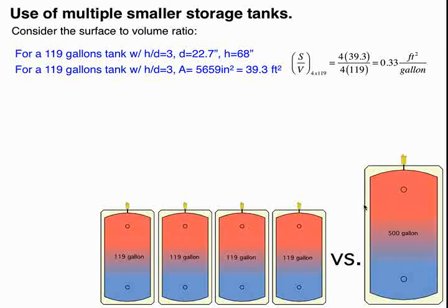Let's talk about multiple tank arrays. The thing you want to be aware of when you're going to multiple smaller tanks versus a larger tank is surface to volume ratio. Obviously, if we put enough smaller tanks in, we can create sufficient volume, but that volume is now in containers that have substantially more surface area. So if we calculate a ratio of the surface area of the tank to the volume of the tank, we have a basis of comparison.